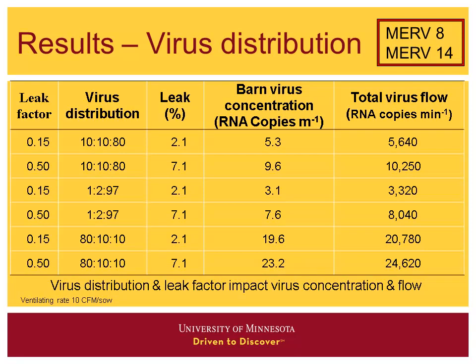Looking at different virus distributions with different filter efficiencies — this case uses MERV 8 plus MERV 14. When we have 80% of virus in the 0.3–1 micron range and we're using a MERV 14, we've got well over 20,000 viruses per minute flowing through, with concentrations around 20. So we've got a lot higher numbers. However, while there may be a lot of virus at that small level, most viruses end up collecting on other particulates, so I'm not convinced that's the best ratio to use.